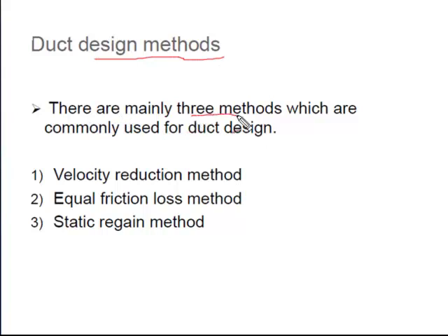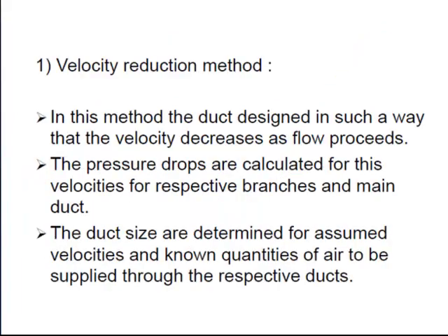There are mainly three methods which are commonly used for duct design. First is the velocity reduction method, second is the equal friction loss method, and third is the static regain method. This is the first method to design the duct, the velocity reduction method. In this method, the duct is designed in such a way that the velocity decreases as flow proceeds.